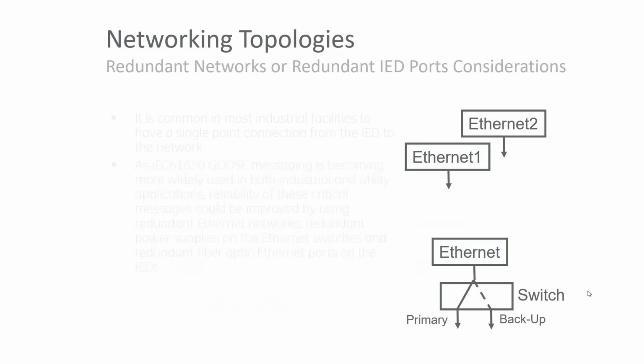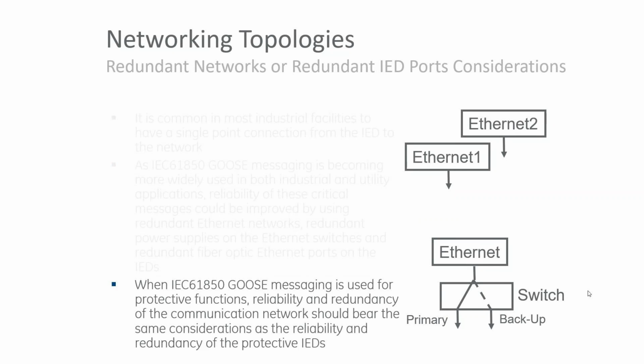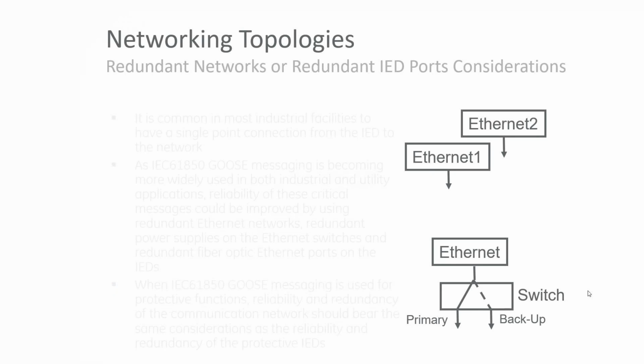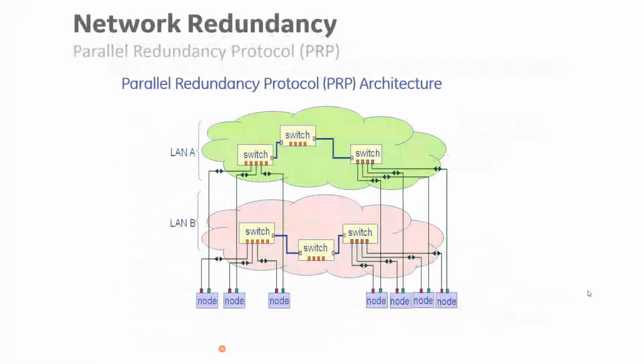I talked about redundant communication in the devices today. It has a primary and backup, so if there is a problem, you can switch over to the primary or backup protection devices. They could be physically separate, or they could be logically within the same device. But the other more robust redundancy protocol is PRP, Parallel Redundancy Protocol. What it does is it takes advantage of those two connections of those devices, which is called a dual attached connection, or DAN, dual attached node.